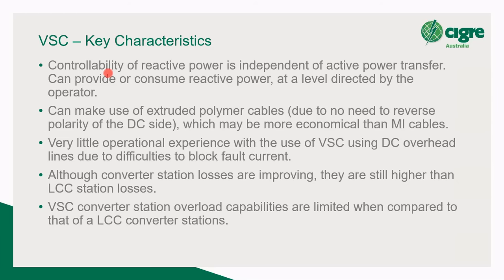You can make use of extruded polymer cables. I didn't really mention this earlier, but with LCC, you need to change the polarity of the voltage to cause power to flow in the other direction. And extruded polymer cables, for reasons beyond my ken, don't like that. But with VSC, in particular symmetric monopole configuration, you have your positive, you have your negative, and you don't need to change polarity. So you can use polymer cables. One disadvantage is very little operational experience with the use of VSC using DC overhead lines.